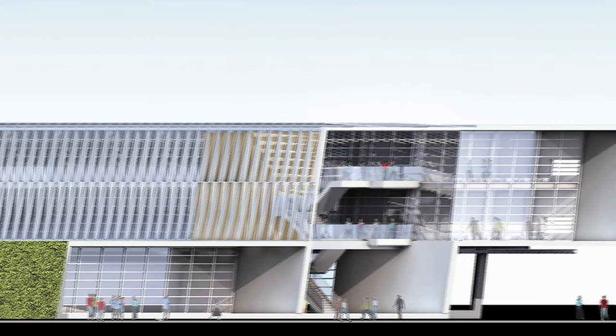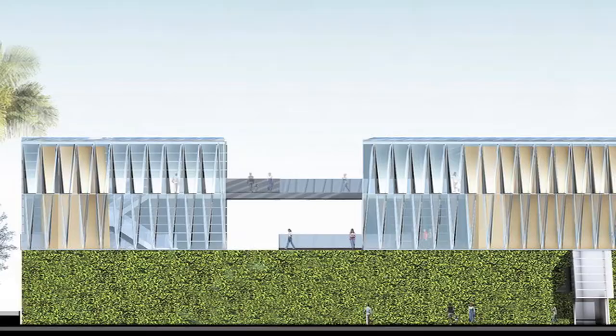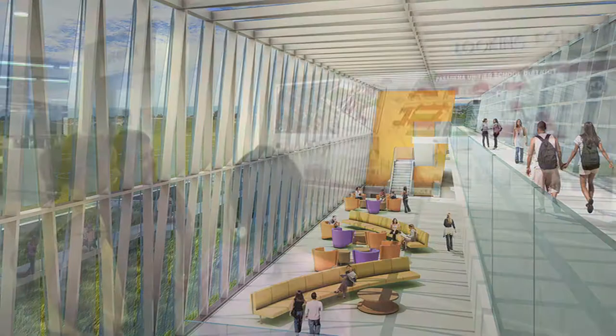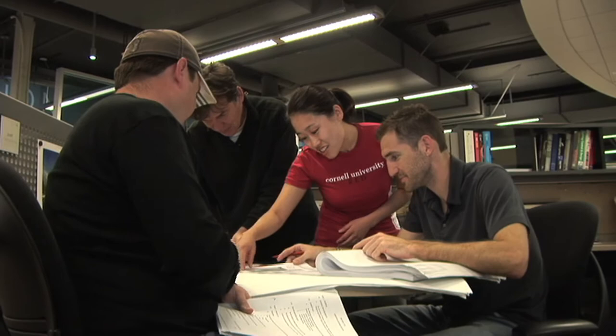It has relatively small classrooms with relatively high occupancy, and trying to maximize and optimize all of those aspects has led us to really unique structural solutions — a low-height building using a concrete structure — and to unique mechanical solutions where we're using 100% outside air, because frankly the ventilation load is the cooling load in a dense classroom in Newport Beach. It's also led to really spectacular architectural solutions, and none of those things would be possible if structural engineers, mechanical engineers, and the architect weren't all closely collaborating and integrating those designs with the client and their goals.